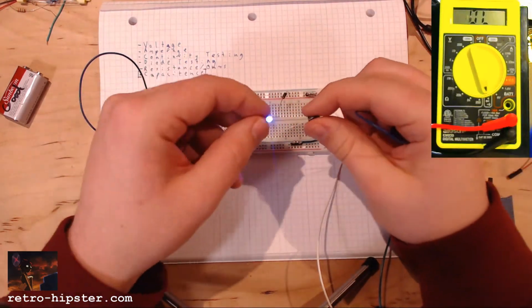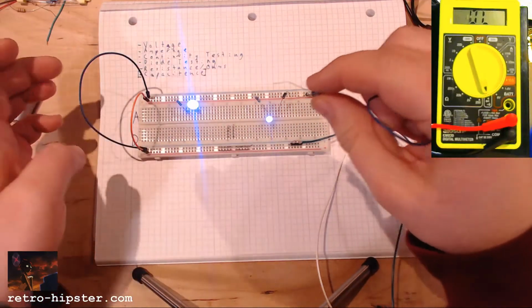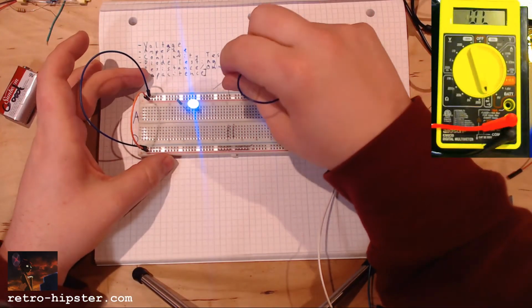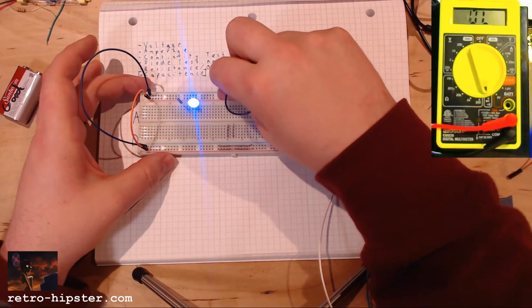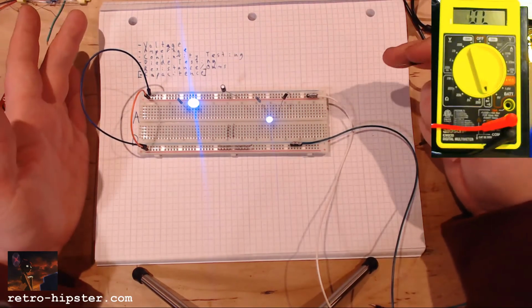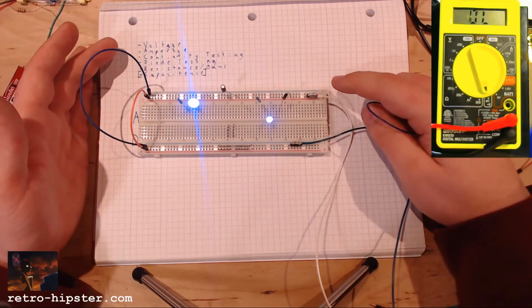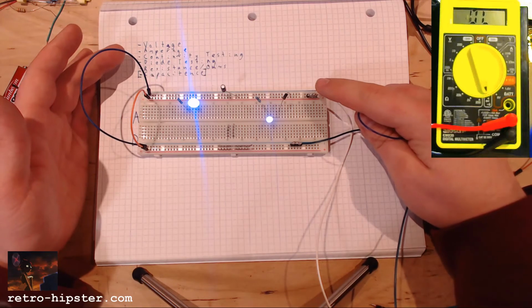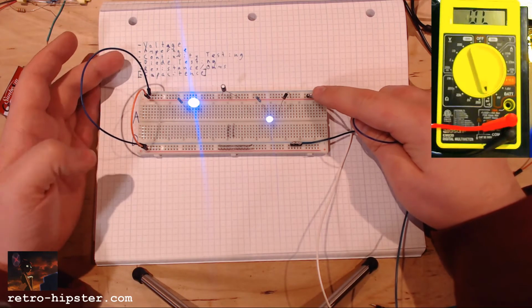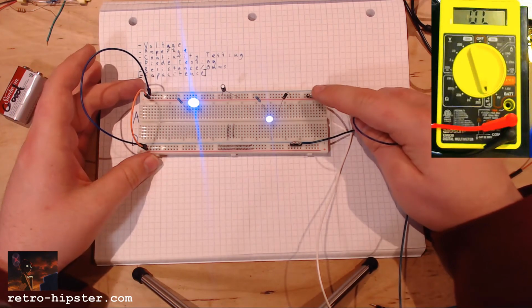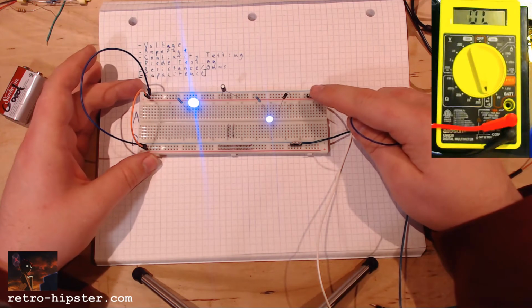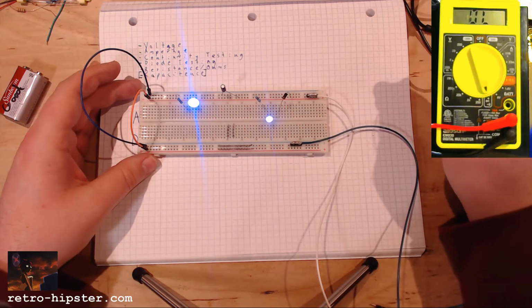Sometimes these become short circuited, and suddenly you'll no longer have power to your circuit. You'll do your amp test and see it's drawing amps, and you'll do your voltage test and it'll show the voltage has gone way down. That probably means you have a short.